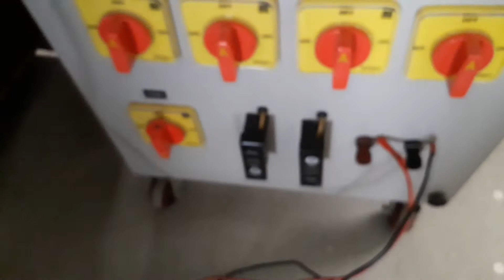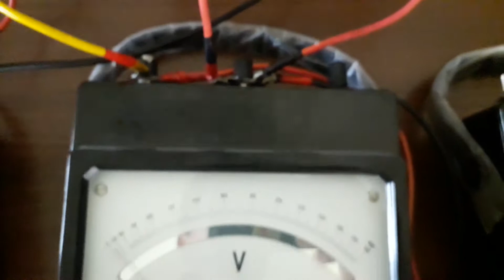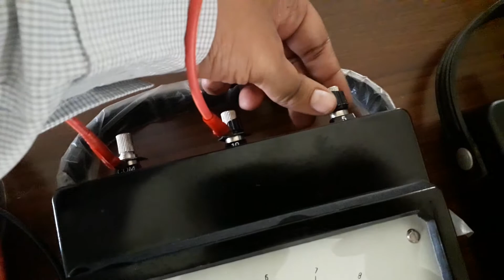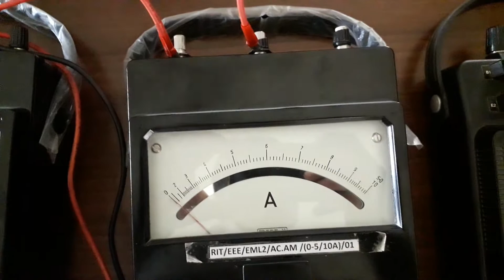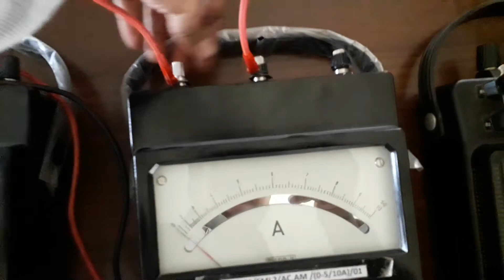Then on the secondary side, from the load, the positive and negative terminals are directly connected as per our circuit diagram, across your voltmeter. From the voltmeter you make the connections like this, and all connections should be very tight because we are going to load the transformer. During loading, if there is a loose connection, it may spark, and sometimes the voltmeter and ammeter get damaged permanently since they are sensitive elements and cannot be reused. So all connections should be very tight, on the secondary side as well.